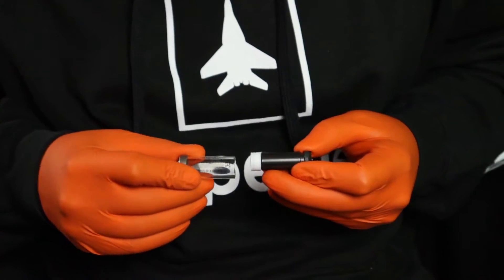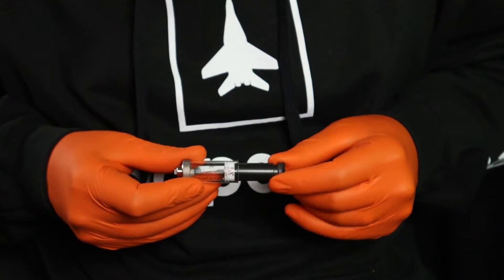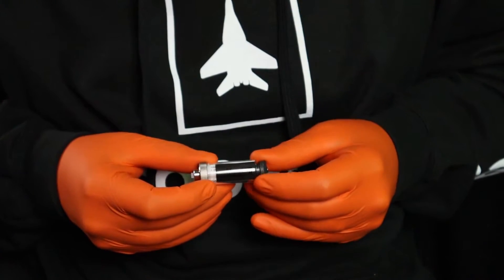Assemble in the reverse order as removed and ensure that all connectors are tight, especially the luer lock connections between the syringe and valve and needle and PTFE. Carefully reinsert the syringe plunger into the syringe body by pushing along the direction of movement. Pushing the plunger at an angle or twisting it may break the syringe glass.